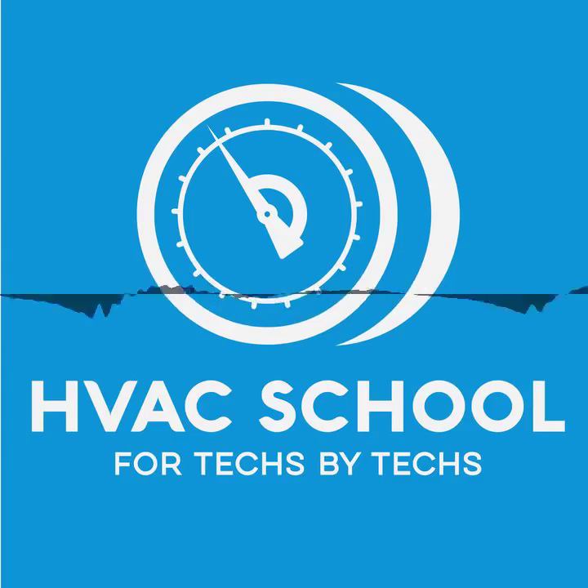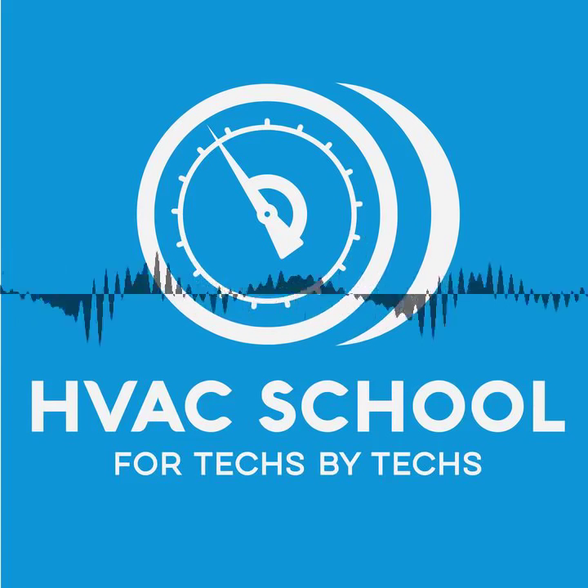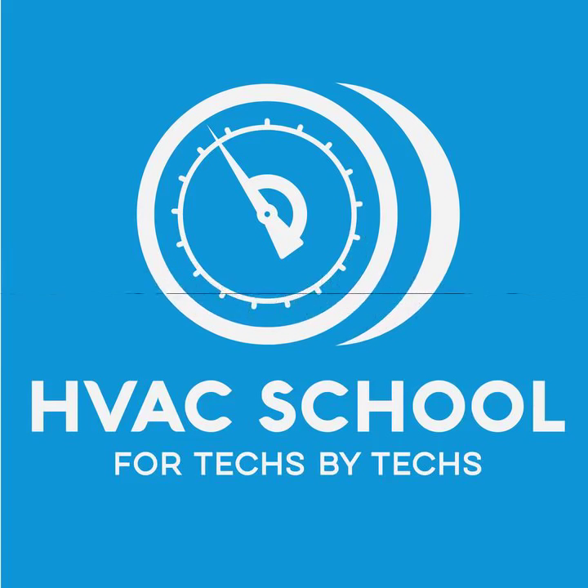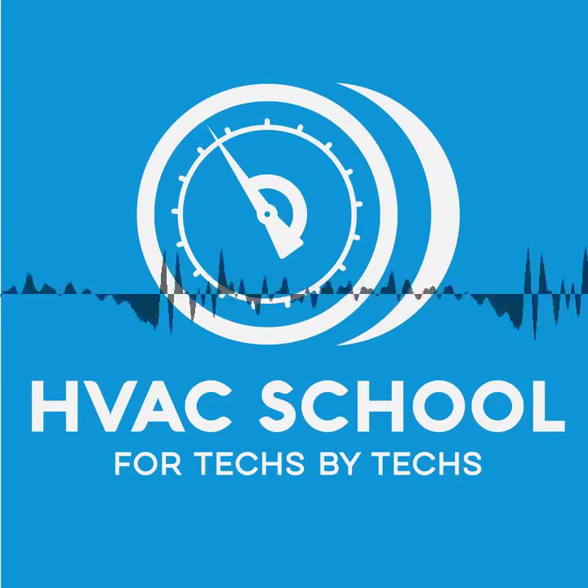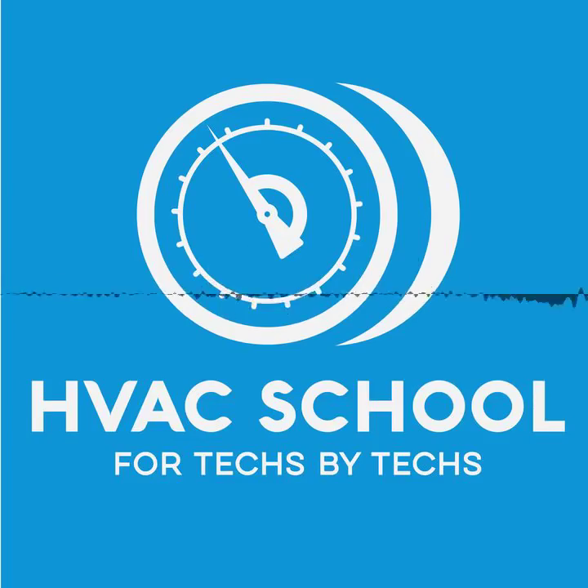So a VRF system, if you go to a commercial site, and we deal with Mitsubishi, Mitsubishi has a line called City Multi. You'll go into commercial buildings and you'll see units that look very much like ductless heads, all over the building, and they all connect back to these large condensers. They call that VRF, variable refrigerant flow. Now, why don't they call it ductless? Well, the main reason is that they're not all ductless. A lot of the heads are actually ducted.